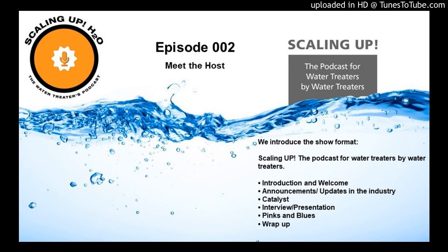So what a lot of us do is choose a non-scaling ion like chloride. Test what's in the tower, divide that by what's in the raw water, and that will give us a more accurate concentration ratio. So what if you're using sodium hypochlorite? Well, obviously you can't use chloride because you're getting chloride contribution from the sodium hypochlorite, so then you have to choose another non-scaling ion.